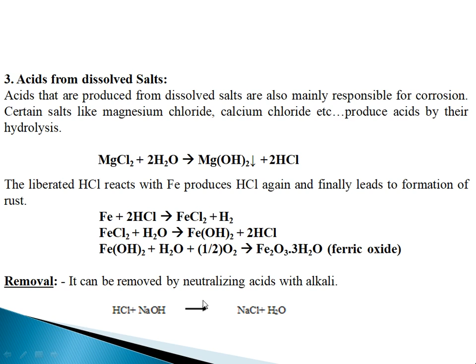The third component responsible for boiler corrosion is acids from dissolved salts. In water containing magnesium chloride, the salt undergoes hydrolysis giving acid. The acid reacts with boiler metal and leads to corrosion. Here HCl is produced by hydrolysis of magnesium chloride. This acid reacts with the boiler iron, forming FeCl2 with removal of hydrogen. FeCl2 dissolved in water forms Fe(OH)2 with HCl. This HCl again reacts with iron metal. It is regenerated, so it is a continuous process. The acid can be removed by neutralizing with a base.